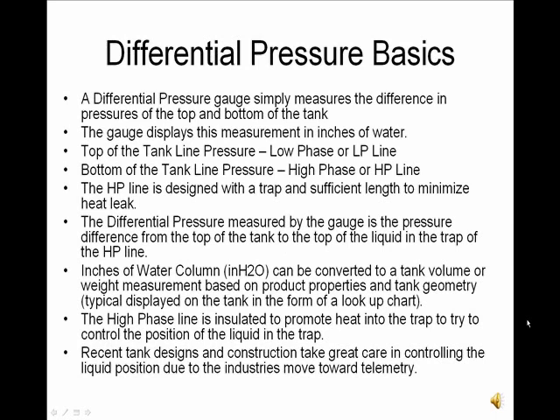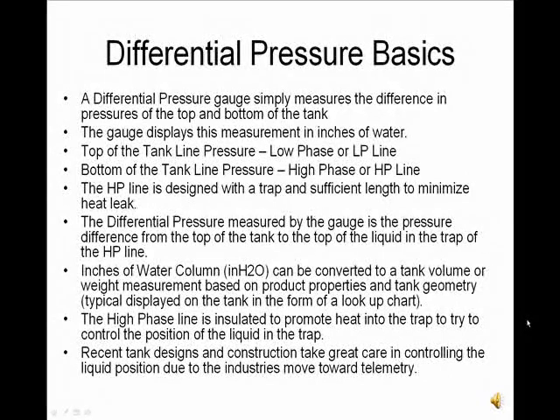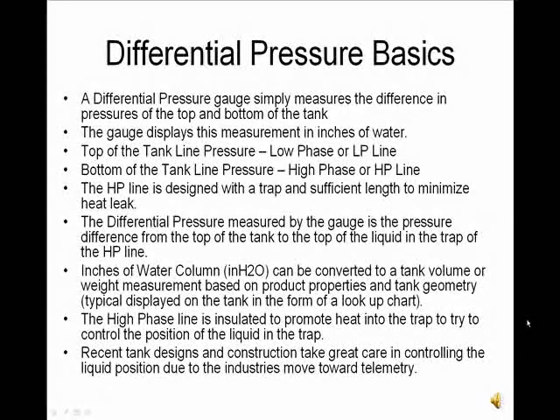A differential pressure gauge simply measures the difference in pressure of the top and bottom of the tank. The gauge displays this measurement in inches of water. The top of the tank's pressure is communicated to the outside of the tank using a small stainless steel line called the low phase or LP line. The bottom of the tank's pressure is communicated using another stainless steel line called the high phase or HP line.